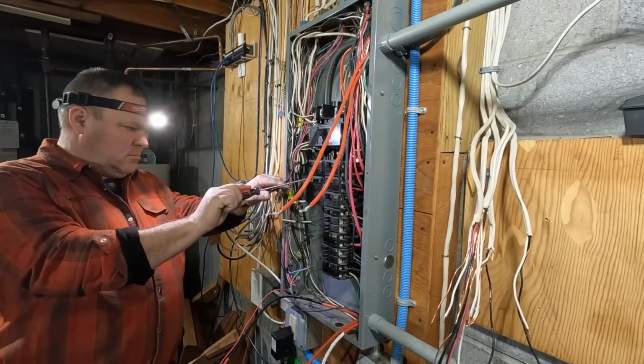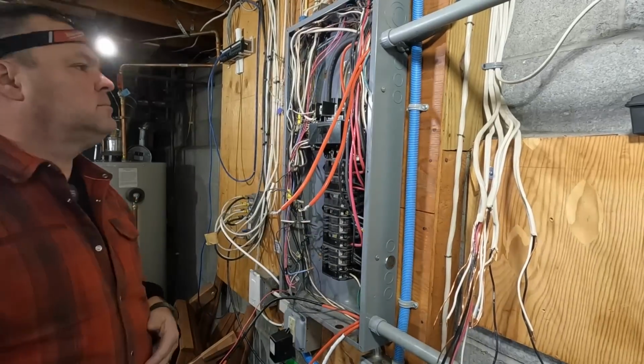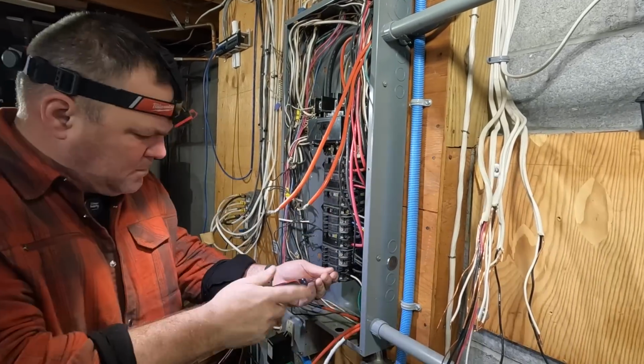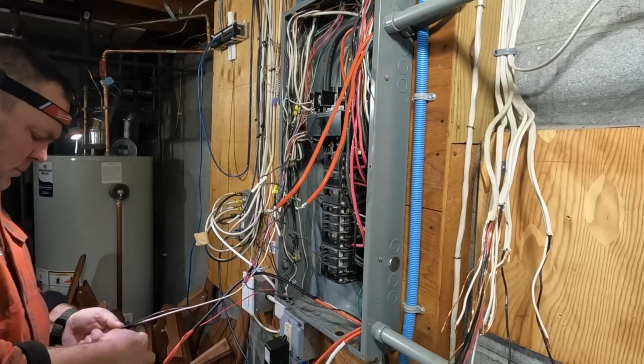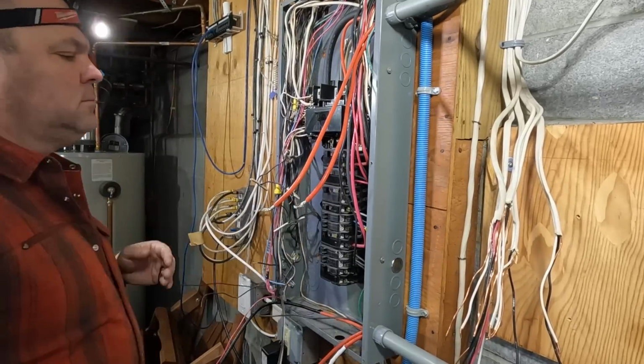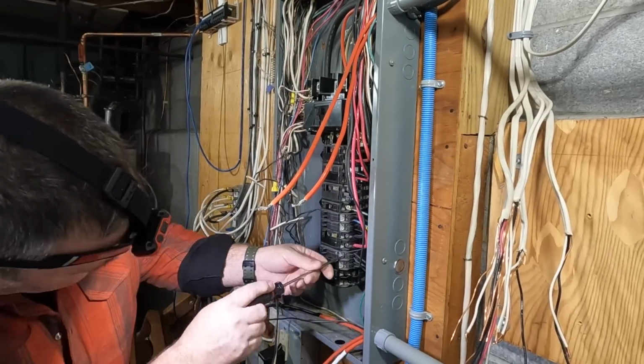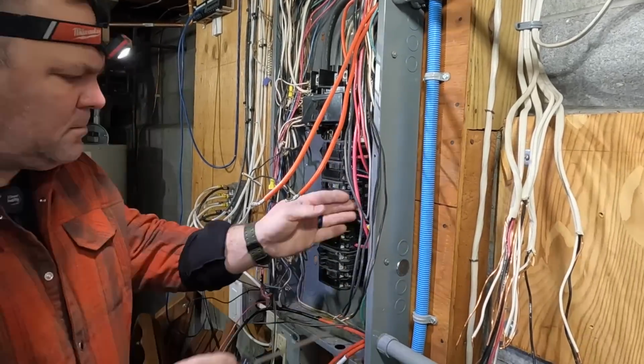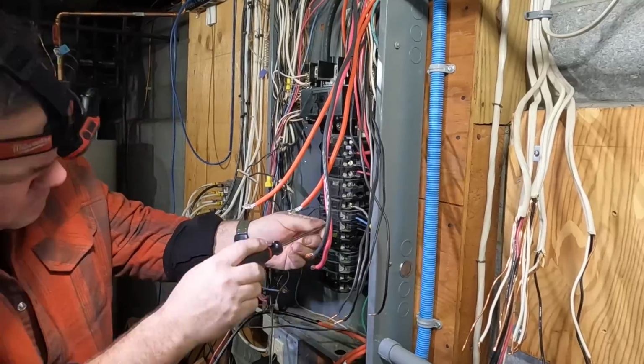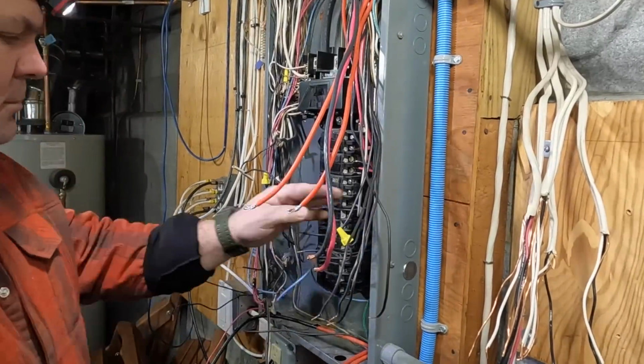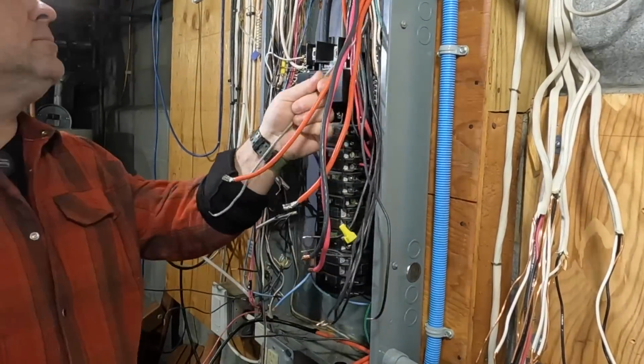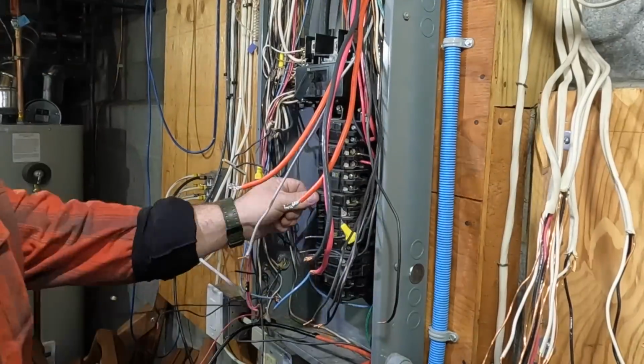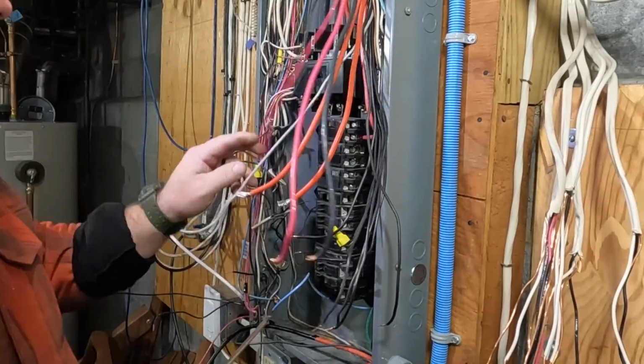So truth be told, anytime I do a panel upgrade or a service upgrade that doesn't consist of armored cable or BX cable or any of the old Romex with the wax around the conductors, that stuff takes a lot of time to get these circuits ready. This panel had a lot of circuits, but all of this was like new wiring, most of it from the 80s and some of it from maybe 15 or 20 years ago.